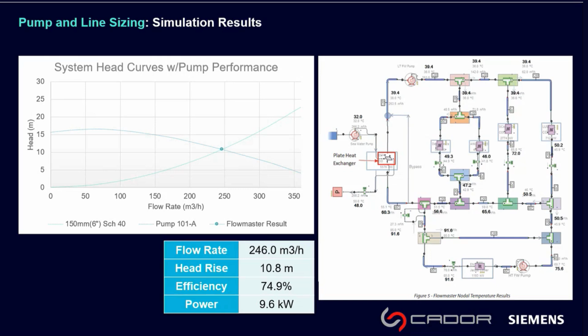On the left, you can also plot a system curve against the pump performance. Running the system in transient shows you where the pump is operating — giving flow rate, head, efficiency, and power. You can easily test different pumps using different settings; if you don't get the right efficiency, you can change parameters like pump speed or other values on the data form.